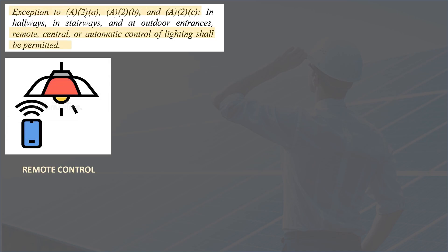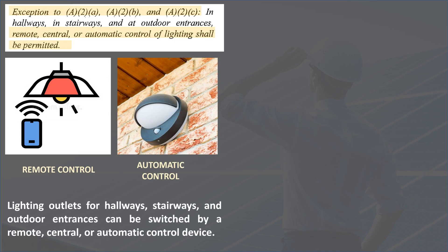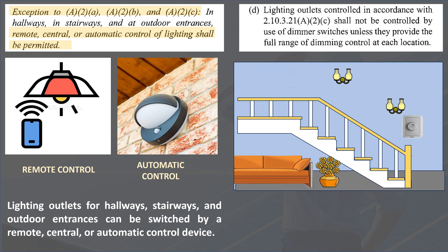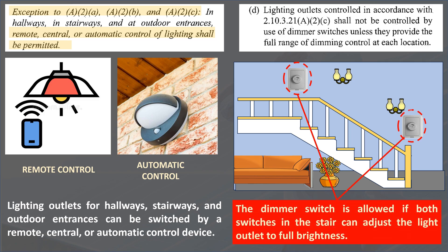As stated in the exception, a remote, central, or automatic control device can switch lighting outlets for hallways, stairways, and outdoor entrances. For interior stairways, a dimmer switch is allowed if both switches on the stair can adjust the lighting outlet to full brightness. This requirement avoids a condition where brightness is set to the lowest illumination at one end of the stairs and cannot be adjusted at the other end.